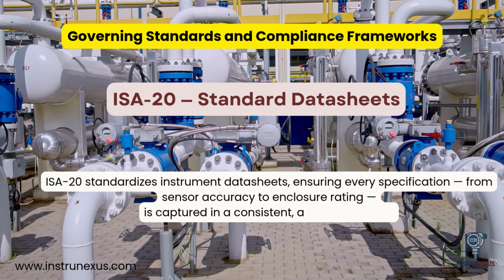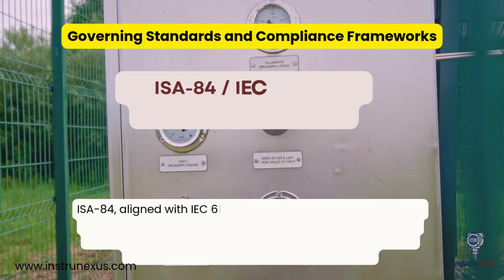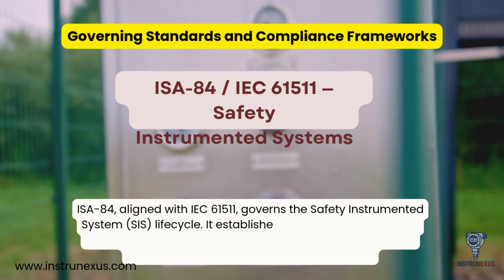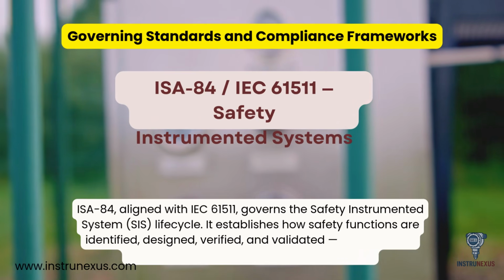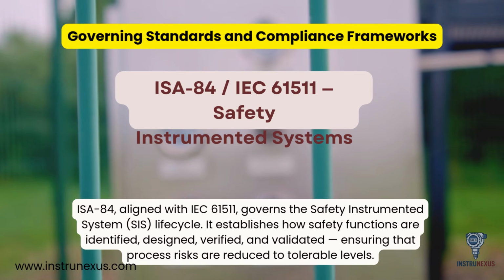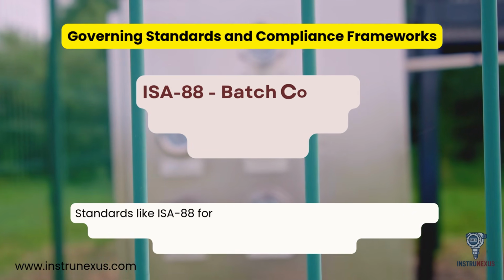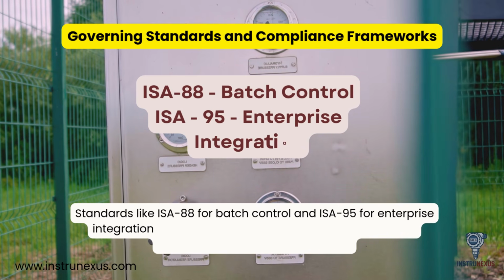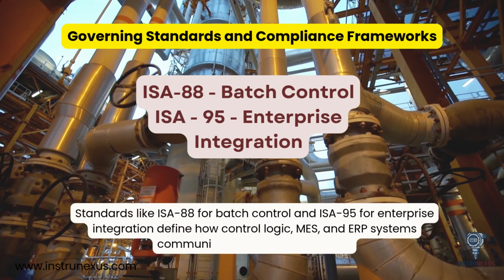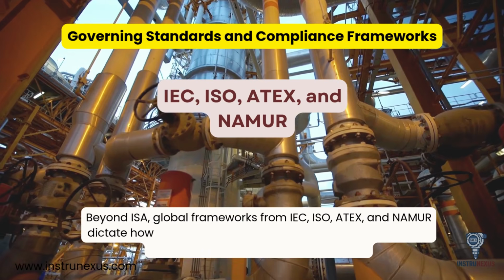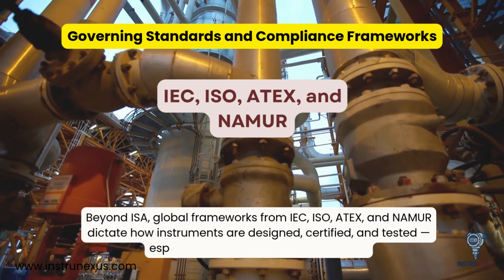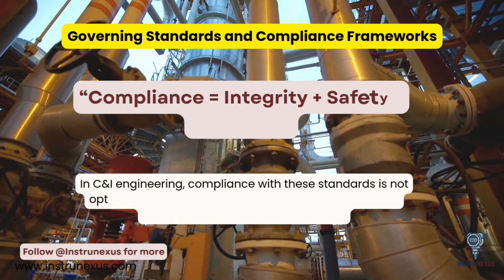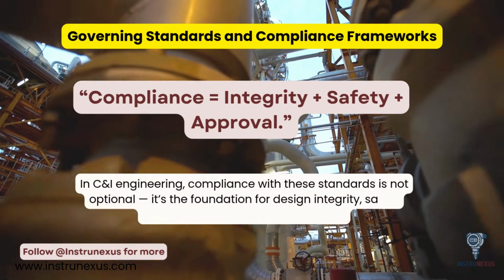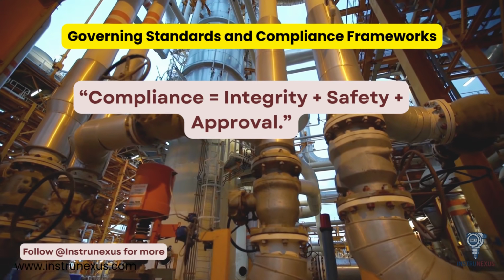ISA 20 standardizes instrument datasheets, ensuring every specification, from sensor accuracy to enclosure rating, is captured in a consistent, auditable format. ISA 84, aligned with IEC 61511, governs the safety instrumented systems lifecycle. It establishes how safety functions are identified, designed, verified, and validated, ensuring that process risks are reduced to tolerable levels. Standards like ISA 88 for batch control and ISA 95 for enterprise integration define how control logic, MES, and ERP systems communicate in complex facilities. Beyond ISA, global frameworks from IEC, ISO, ATEX, and NAMUR dictate how instruments are designed, certified, and tested, especially for hazardous environments. In C&I engineering, compliance with these standards is not optional. It's the foundation for design integrity, safety assurance, and regulatory approval. Following standards ensures that your design speaks the same language anywhere in the world.